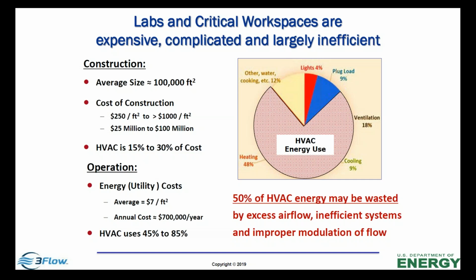So labs can be very expensive to build, and the HVAC in that lab can be 15 to 30% of the cost of building it. Now operationally, there's the utility cost — an average around the country might be $7 per square foot, an annual cost of the building of $700,000 a year. Some buildings, which are bigger and more dynamic, costs are going to be greater than that. And the HVAC use can be 45 all the way up to 85%.